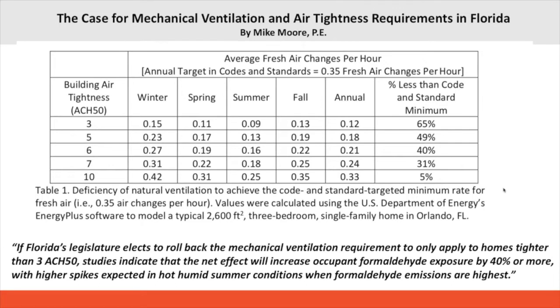And right here, Mike included this in his letter that he wrote to HVI about how tight these Florida houses are getting, and that studies were going to indicate that the net effect will increase occupant formaldehyde exposure by 40%, and then even higher in the hot, humid conditions when formaldehyde emissions are much higher. So as we discussed before, the higher the RH is in a home, the quicker our materials in the house, cabinets, furniture, building materials, are going to off-gas that formaldehyde. So mechanical ventilation is very important in our tighter homes. We have to dilute that indoor air pollution.